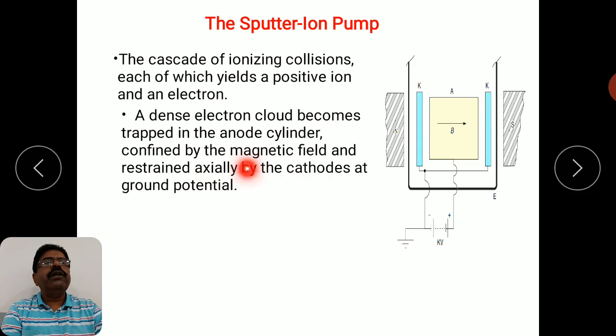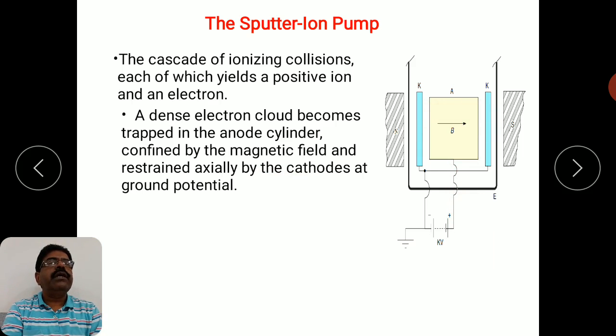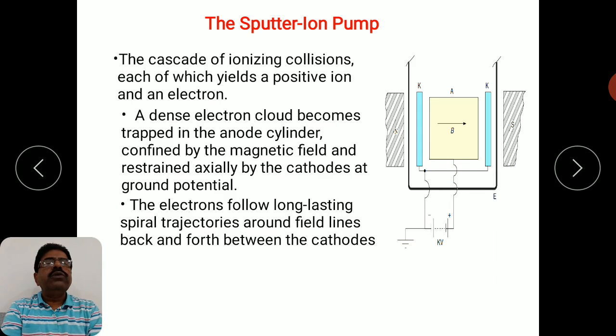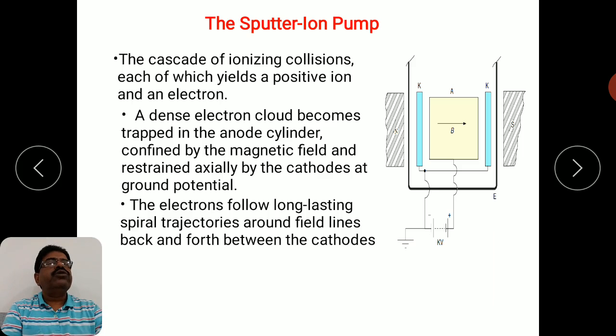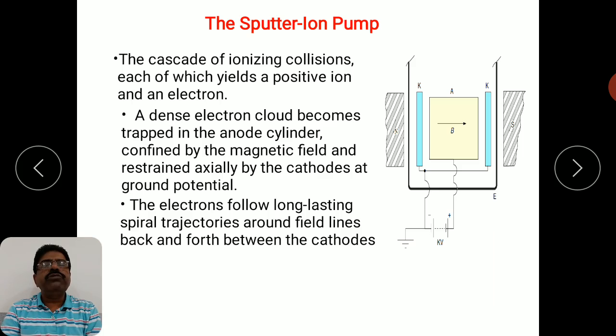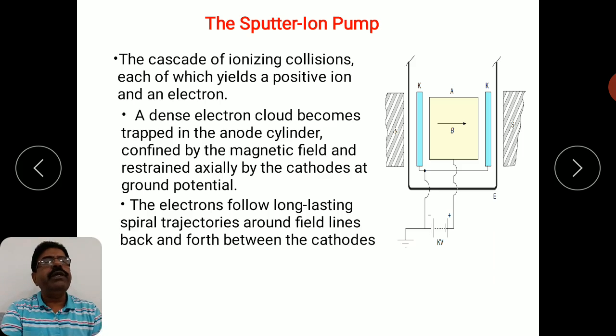The electron cloud is confined by the magnetic field and restrained axially by the cathodes at ground potential. The electrons follow long-lasting spiral trajectories around the field lines, moving back and forth between the cathodes, continuously colliding with gas molecules and ionizing them — producing a new electron-ion pair each time.